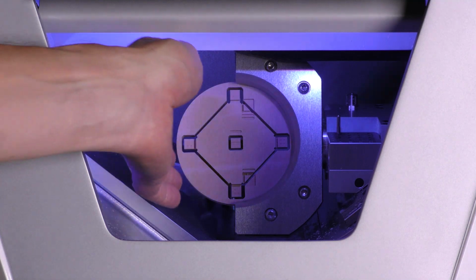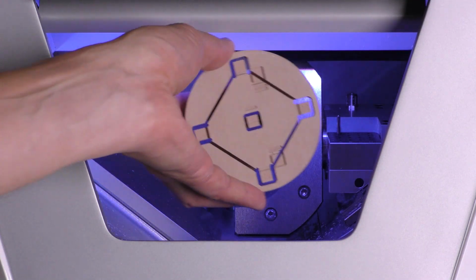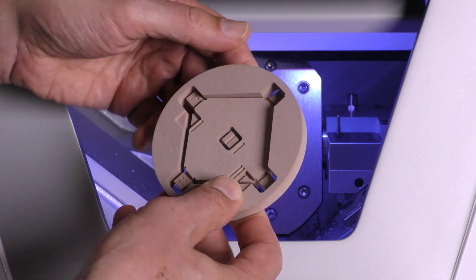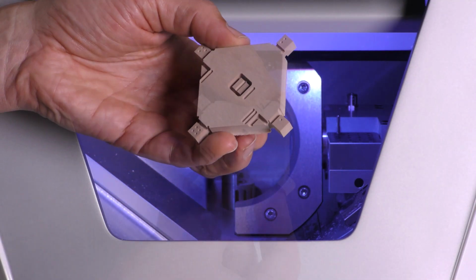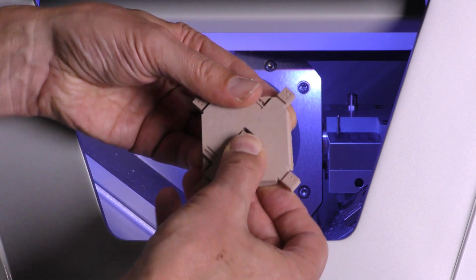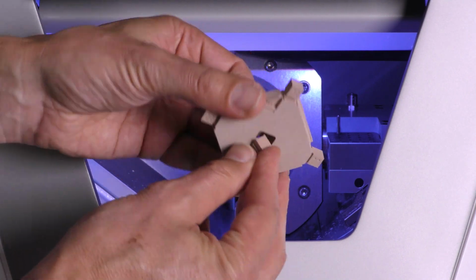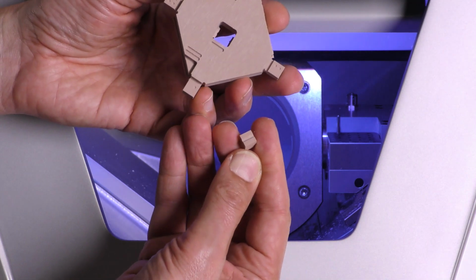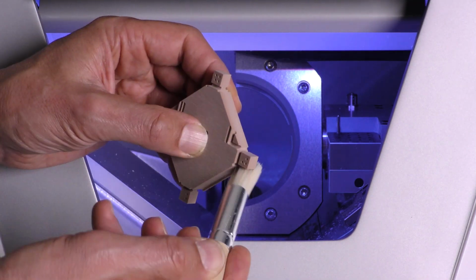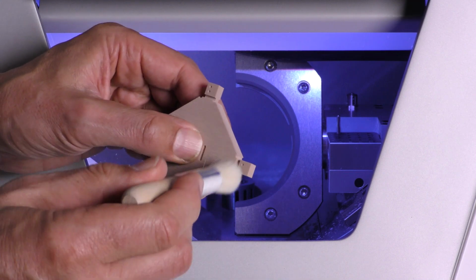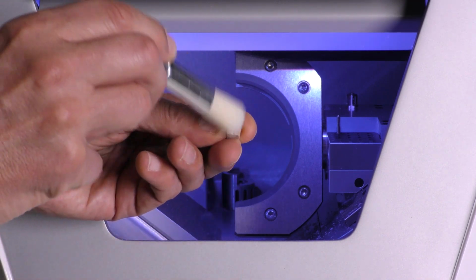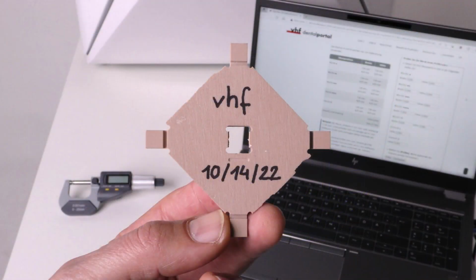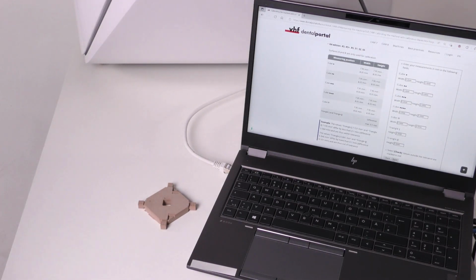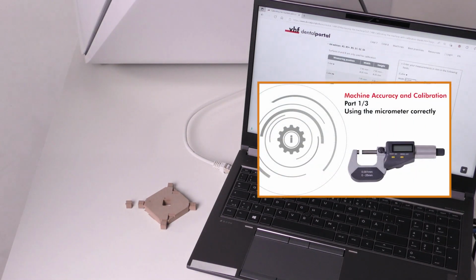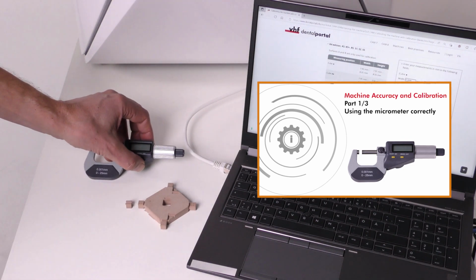When the job is completed, remove the disc from the holder and separate the test specimen from the disc. If your machine is an E5, N4 Plus, R5, K5, K5 Plus or from the S series, separate the measuring spot, M, from the test specimen as well. Clean the individual parts of the test specimen with a brush. Make sure there are no machining residues left before measuring. Label the test specimen with a name and current date. Prepare and use the micrometer as shown in part 1 of 3 in this video series, Using the micrometer correctly. You can find the link in the video description below.